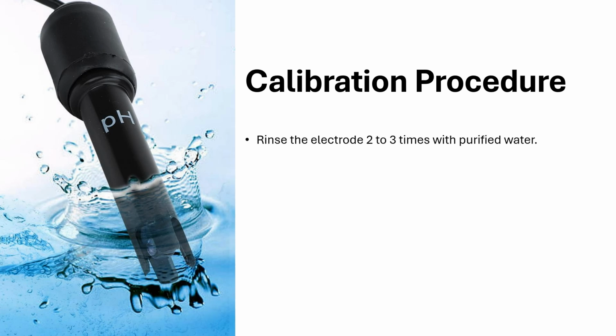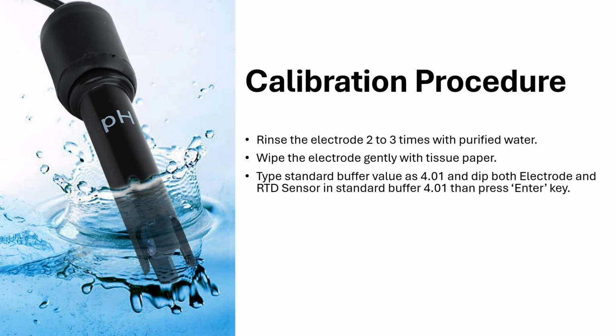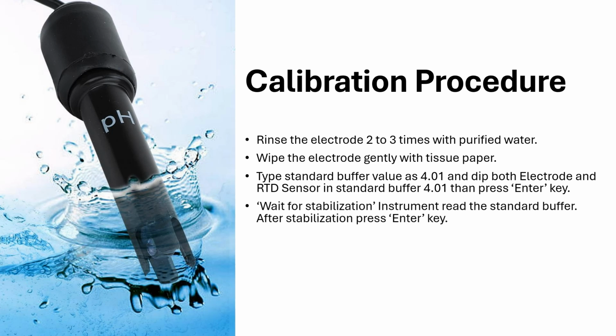After finishing the calibration with the 1.68 pH buffer, to continue the calibration, start by rinsing the electrode 2 to 3 times with purified water to ensure it's clean for accurate reading, right? Then again wipe the electrode gently with tissue paper, right? Next, type the standard buffer value 4.01 into the pH meter, then dip both the electrode and the RTD sensor into the standard buffer solution of pH 4.01, right? And press the enter key to start the reading process. This will show wait for stabilization. This means the instrument is reading the standard buffer and will display the stabilized reading shortly, right? Once the reading is stable, press enter to confirm the calibration for this buffer, right?